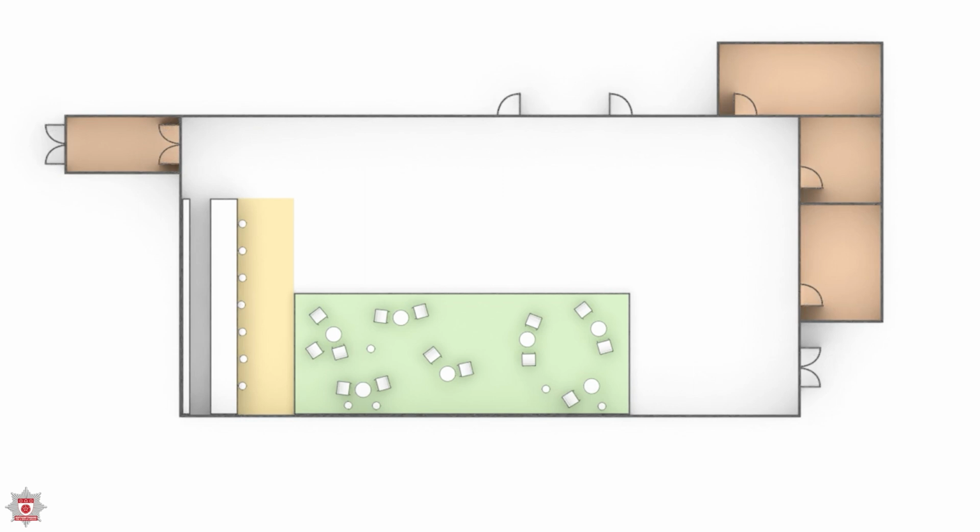As we have mentioned previously, the doors that lead to final exits should be measured. If an exit door leads to a final exit door via a corridor, as seen here, then the narrowest point is the measurement for exit width. If there is a single exit door leading out to a double exit door, we will measure the single exit width as the exit width, as this is the narrowest point along the exit route and will allow for fewer amount of people to exit safely.